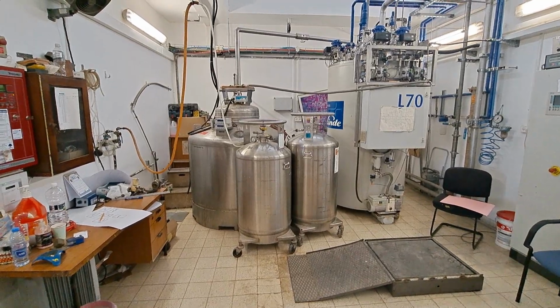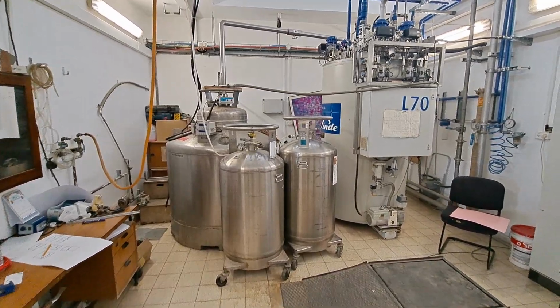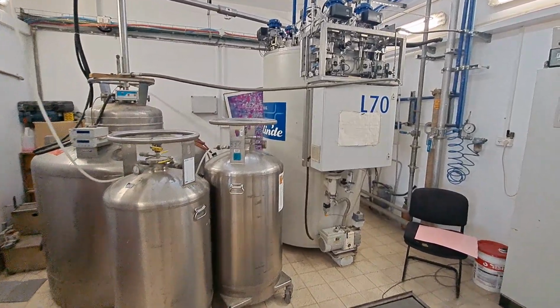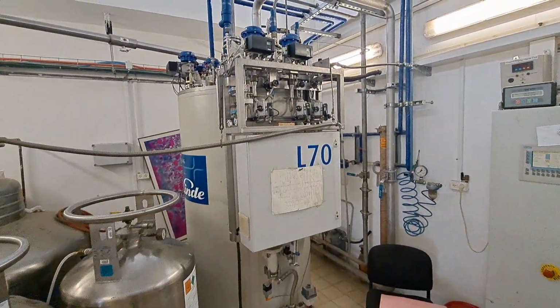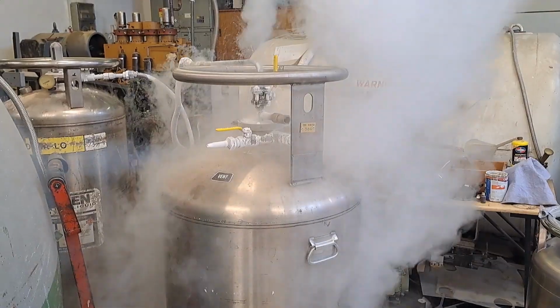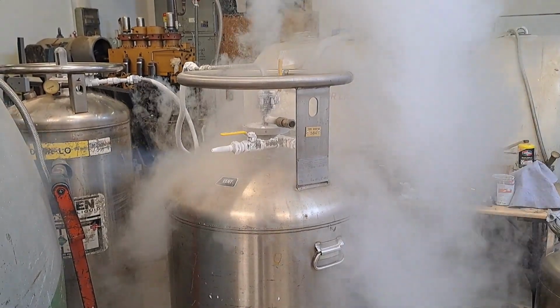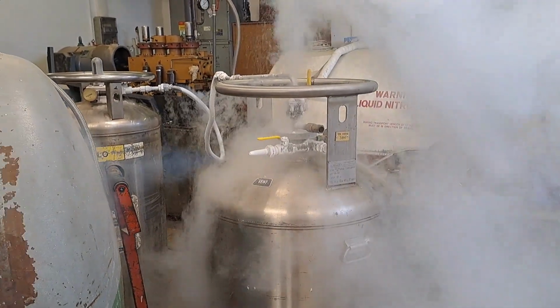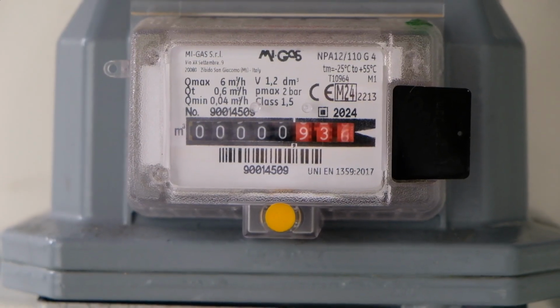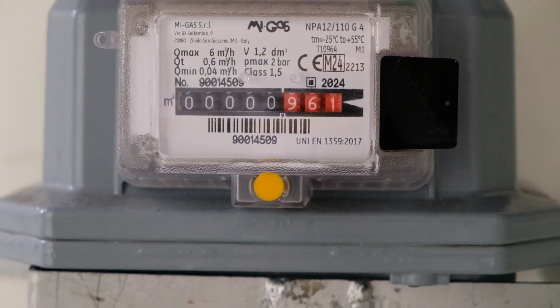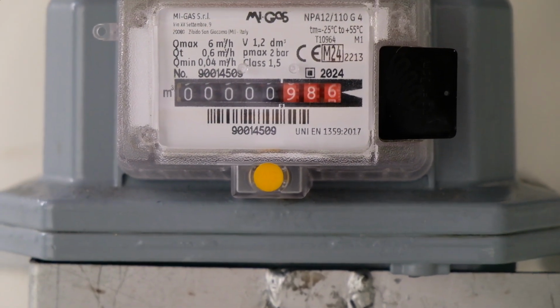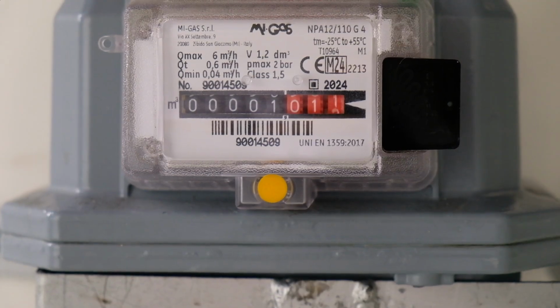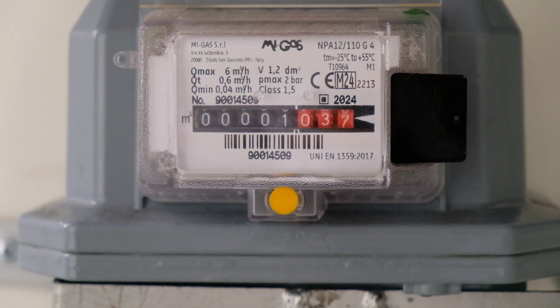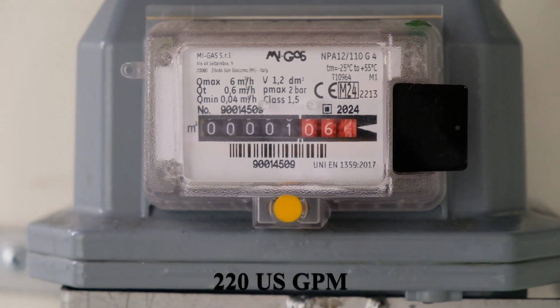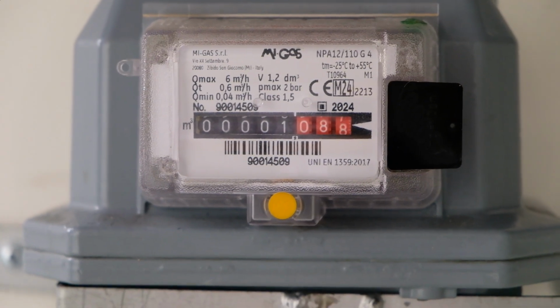From the chiller, the liquid helium is transferred to a 1,000-liter holding tank ready to transfer to mobile dewars for distribution. Before filling, the mobile dewars are pre-cooled with liquid nitrogen. The condensed liquid is then siphoned out and the dewar flushed with helium gas to remove nitrogen before cooling with liquid helium. On cooling the NMR magnet, the flow rate peaked at 50 meters cubed per hour and the sacks filled up.